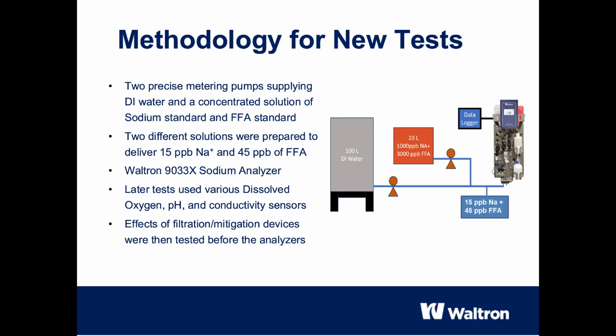Here you can see our experimental setup. We used 2 high-precision dosing pumps that mix deionized water and a concentrated solution of sodium and FFA standards. This allowed us to ensure a stable concentration of 15 ppb sodium and 45 ppb FFA at the inlet of an unmodified Waltron 9033X sodium analyzer. All data was collected by a data logger. In later phases of the project, we expanded this setup to also investigate the effects on dissolved oxygen, pH, and conductivity sensors, and to test various mitigation and filtration technologies. This setup allowed us to investigate the effects of the FFAPs under controlled and reproducible conditions.